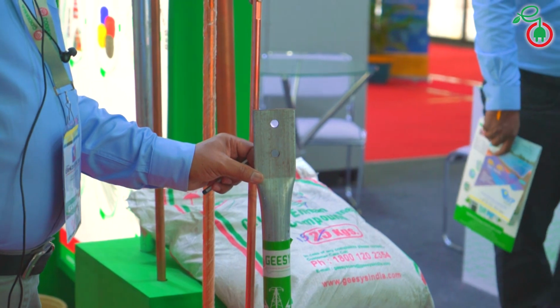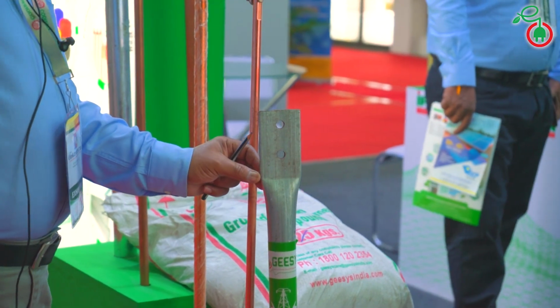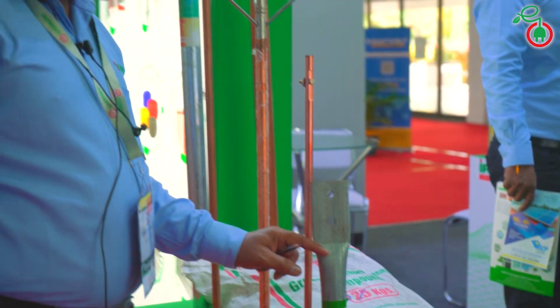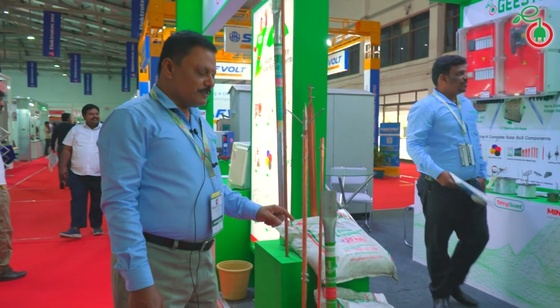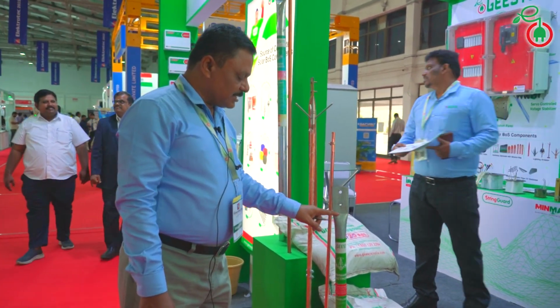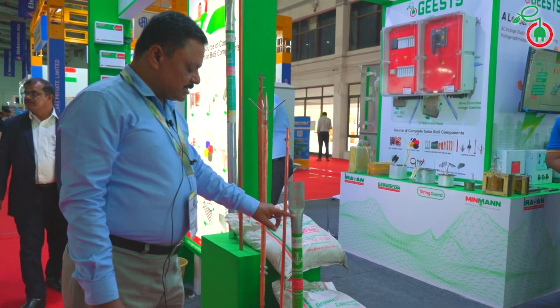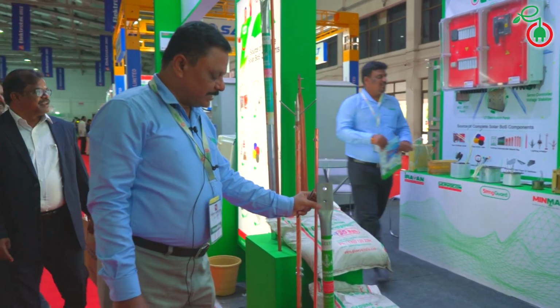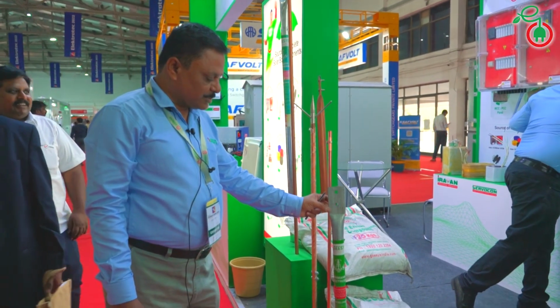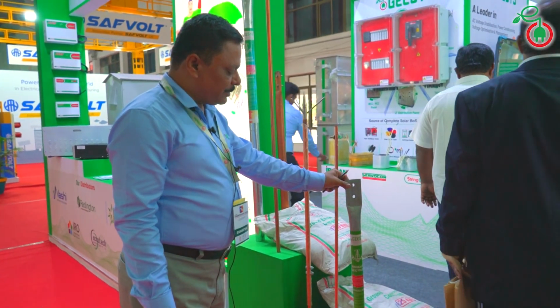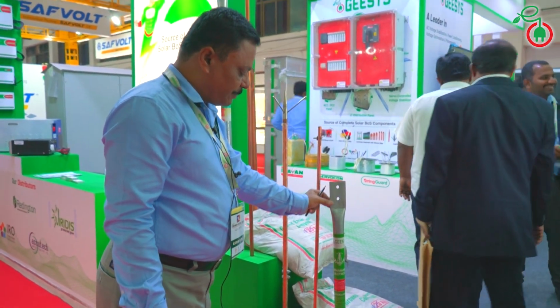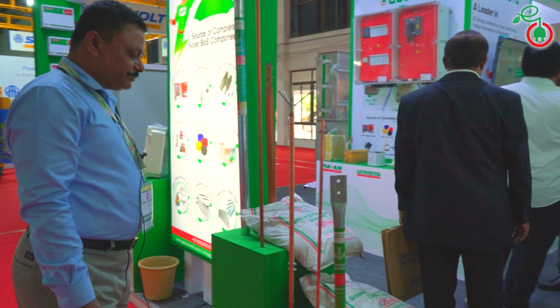In case of other earthing electrodes, where it is a pipe in pipe, strip in pipe, or wire in pipe, there is always a possibility of disconnection at the welding level. In this case, there is no welding done and no additional attachment, so as lightning happens, the dissipation happens continuously without any breakage.